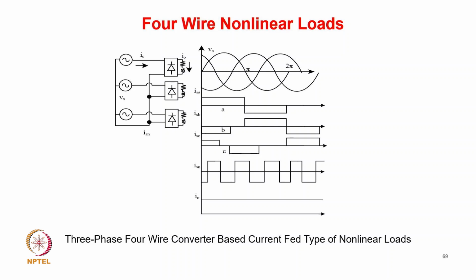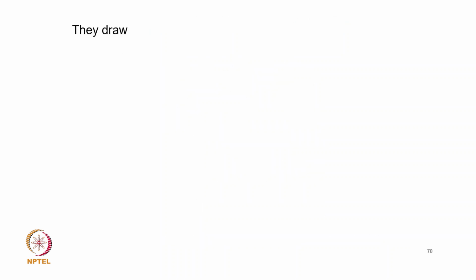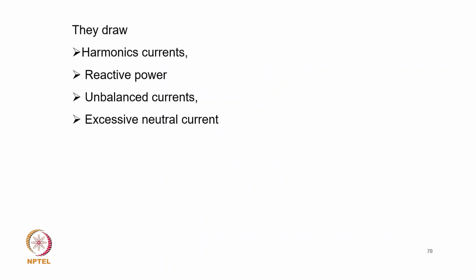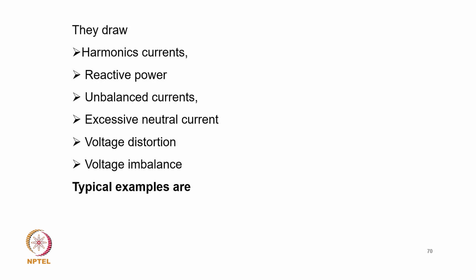You can even have a square wave current, where the net neutral current is the same as the phase current but at 3 times the frequency, as you can see here. There we have harmonic current, reactive power, unbalanced current, excessive neutral current, voltage distortion, and voltage unbalance.